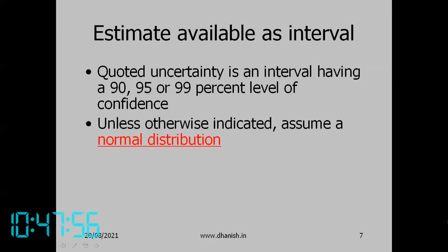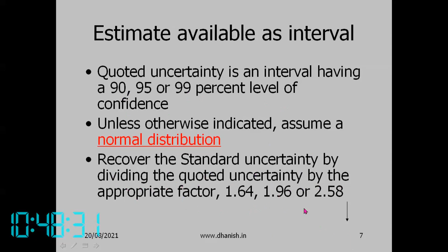So if a 90% uncertainty interval is given, then simply divide by the appropriate factor. This is actually a coverage interval, so the coverage interval divided by that factor will give the standard uncertainty. Recover the standard uncertainty by dividing the quoted uncertainty by the appropriate factor, which may be 1.64, 1.96 or 2.58. Whatever is given, divide by the appropriate factor, and you get the standard uncertainty.